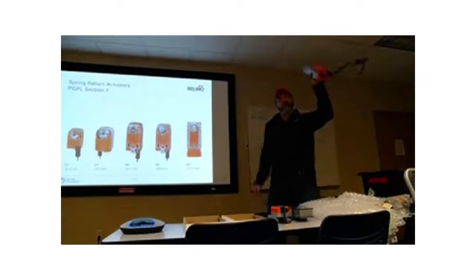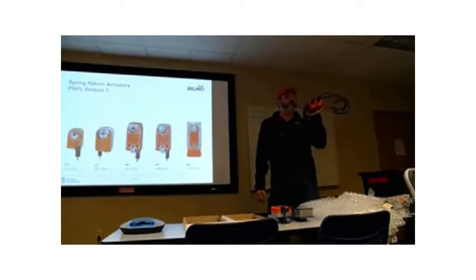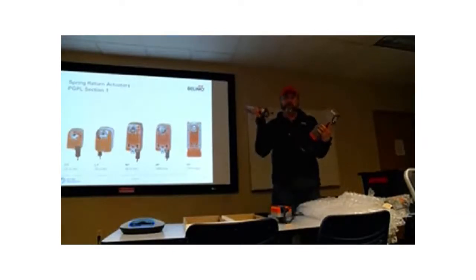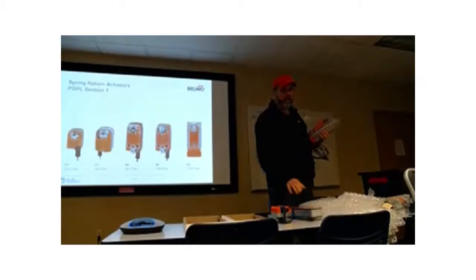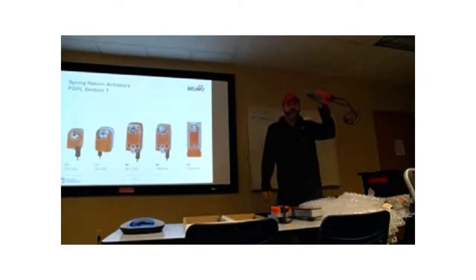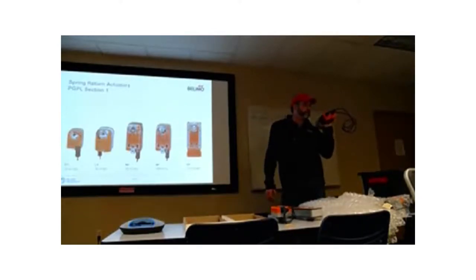The EF here is 267. So the higher math says one of these is equal to 2 of these. The reason I'm mentioning this is if you see an installation where you have 2 damper actuators like this on the same shaft, my recommendation is to replace it with one of these. What's the price difference? It's pretty comparable. In fact, I think this is a little less expensive than 2 of these.